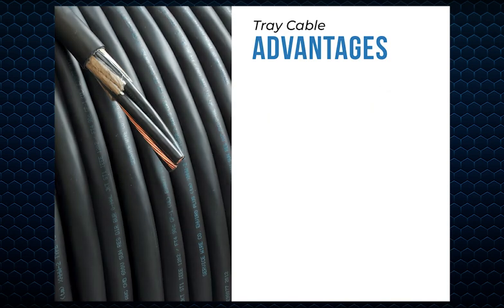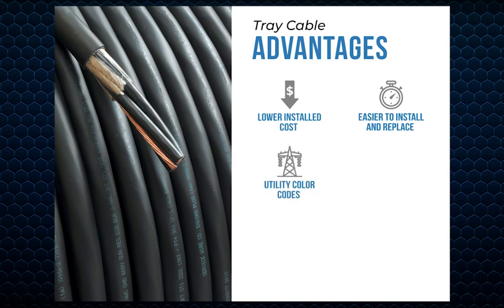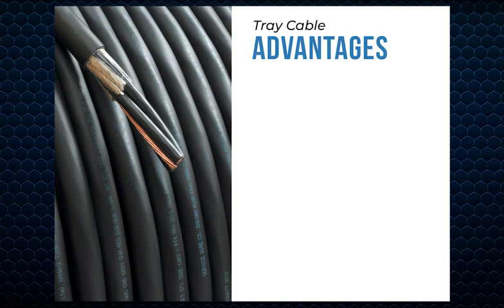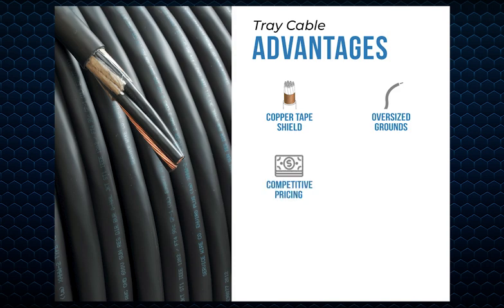In summary, tray cable advantages are simple. It offers lower installed costs than conduit and wire and is easier to install and replace. Plus, Service Wire's tray cable is available in utility color codes, unusual conductor counts, and 4 conductor power sizes. You can specify 2 types of copper tape shielding, request oversized grounds for cables run in parallel, and get competitive pricing compared to THHN tray cable power sizes. All of these advantages create efficiencies in manufacturing and result in lower overall costs.